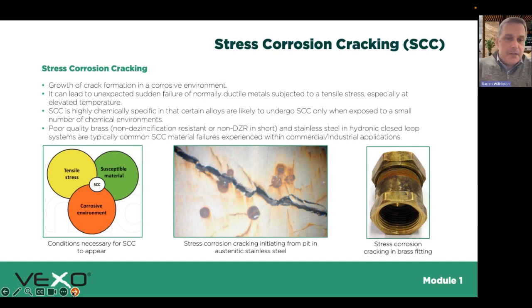We need a susceptible material. So in the case of a chill water system, it will be chill water typically. You may have had a bacterial issue, and as a byproduct, they create ammonia. Unfortunately, that ammonia becomes part of the corrosive environment for the system. So the susceptible material in this case would be a brass fitting. We see it a lot less than we used to nowadays, because there's DZR brass. But there was a period where engineers would specify bronze on chill water just to be completely covered, I suppose, rather than a brass. And if you have a poor quality brass, you could have failures.